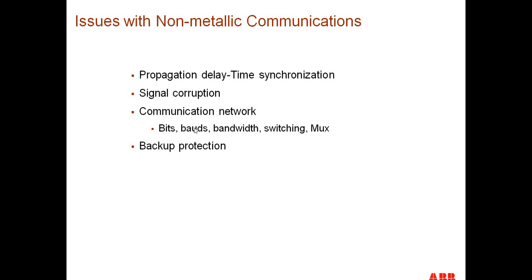But we also are able to incorporate backup protection into our current differential scheme. So that if we do lose communications for some reason, we can rely on some backup protection, whether it be a simple overcurrent relay or whether it be a distance relay that we use to back up the current differential if we should lose the communications channel. So there are remedies to this.